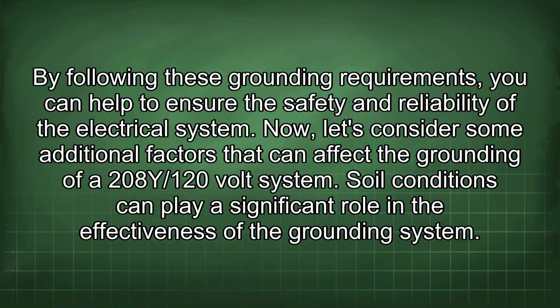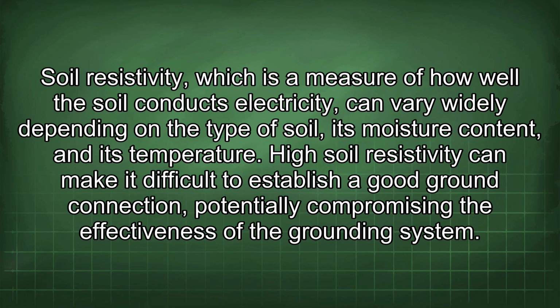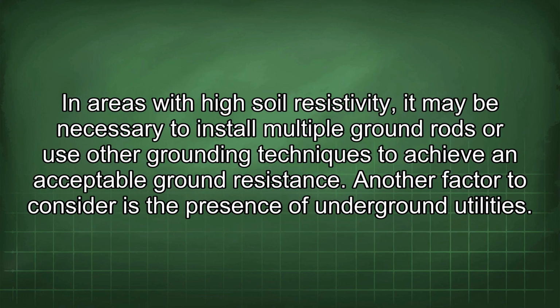Now, let's consider some additional factors that can affect the grounding of a 208Y/120 volt system. Soil conditions can play a significant role in the effectiveness of the grounding system. Soil resistivity, which is a measure of how well the soil conducts electricity, can vary widely depending on the type of soil, its moisture content, and its temperature. High soil resistivity can make it difficult to establish a good ground connection, potentially compromising the effectiveness of the grounding system. In areas with high soil resistivity, it may be necessary to install multiple ground rods or use other grounding techniques to achieve an acceptable ground resistance.